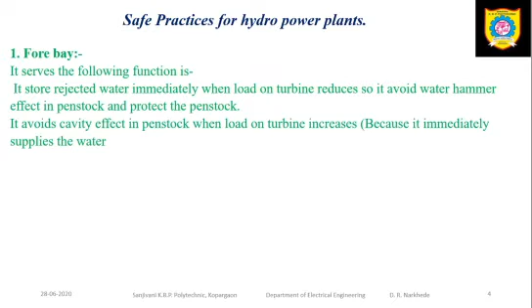Now, what are the safety practices used at a hydroelectric power plant? One is that a forebay is used. What is the function of the forebay? It stores the rejected water immediately when the load on the turbine reduces, so it avoids the water hammer effect in the penstock and protects the penstock. So this forebay is very important. If you do not use the forebay, then your penstock may get damaged.